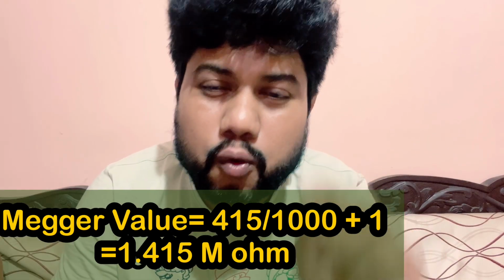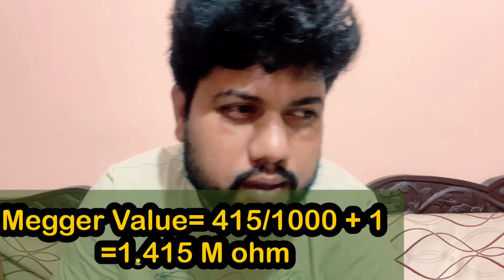So the minimum or lowest insulation resistance value always comes with the voltage level of a particular motor. Say for example, if the voltage level is 415 volt, then the lowest megger value comes around 0.415 plus 1 equals 1.415.